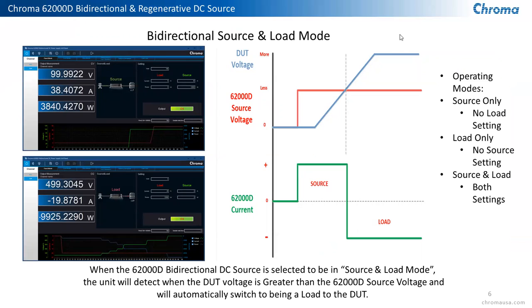The bidirectional source and load, if you're not familiar with how it works, it can be used as a load. It can be used as a source. The rating for both the load and the source for power are the same. So you can use it as an 18 kilowatt load or an 18 kilowatt source, and you have the entire current range for the load and for the source, as well as the entire voltage range too. So when you program this unit, we have the ability to set it just as a load or just as a source and use it independently.